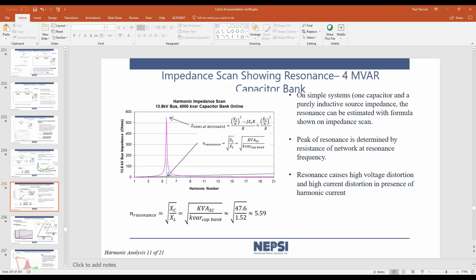You can picture shifting this curve from where it's located, which is at the 5.59, to the left to near the 5th, and by shifting that impedance curve just a little bit, you can have a very significant change in your results. So a system like this would be an example where the results might show it's okay within 519 limits, but by doing some perturbation analysis, changing the impedances just a little bit, you can picture that curve shifting to the left, causing a resonance and then resulting in high distortion.